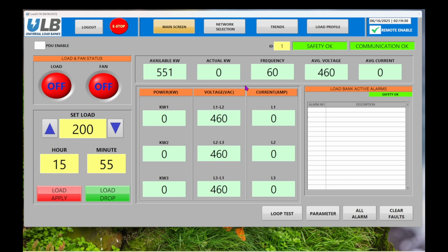To control the load bank, first select Remote Enable. Then set the desired load, hour, and minutes. Press the Load Apply button to apply the load, and press Load Drop to remove it. Pressing E-Stop will shut off both the load and the fan immediately. You can monitor system behavior over time by using the trend screen.